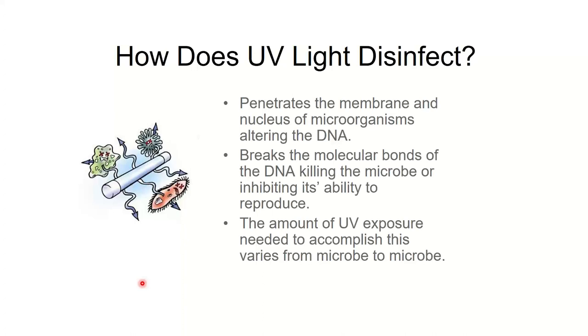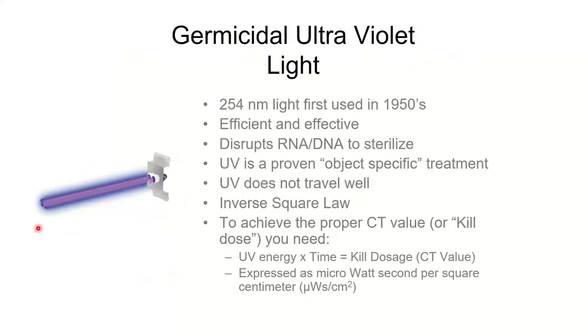Same thing's going to happen in our buildings, in our airstreams. The UV light is going to kill the germs if the UV light can shine on the germs. Got to get the UV light to the germ. Most of these bulbs are going to use a 254 nanometer wavelength, which is in the UVC spectrum. And the important thing for our purposes today is how much light do I need to kill something, specifically today, COVID. I call it the kill dose.